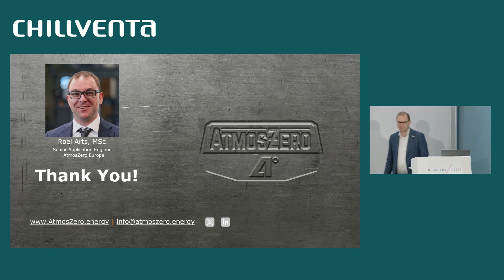The question is about COP. Our target COP — which we do not yet reach with the first pilot system delivered — is a COP of 2 when lifting from 15°C ambient air to 150°C steam. It's a challenging target — more than 60 percent of Carnot. At our first try we have some optimization still to reach it, but that's the target. Thank you again for your attention and I hope to see you at our booth.